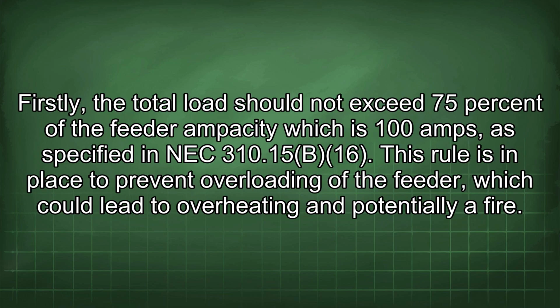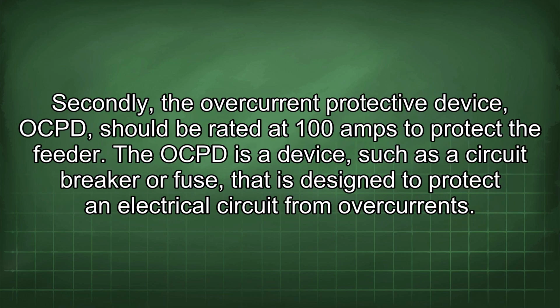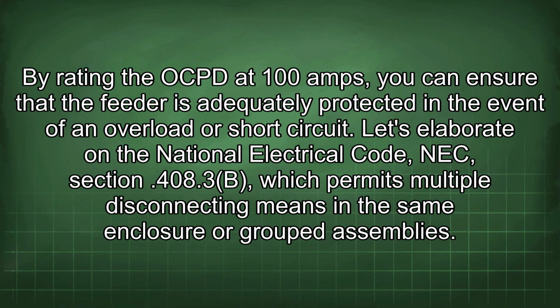Firstly, the total load should not exceed 75% of the feeder capacity, which is 100 amps, as specified in NEC 310.15(B)(16). This rule is in place to prevent overloading of the feeder, which could lead to overheating and potentially a fire. Secondly, the overcurrent protective device, OCPD, should be rated at 100 amps to protect the feeder. The OCPD is a device, such as a circuit breaker or fuse, that is designed to protect an electrical circuit from overcurrents. By rating the OCPD to 100 amps, you can ensure that the feeder is adequately protected in the event of an overload or short circuit.